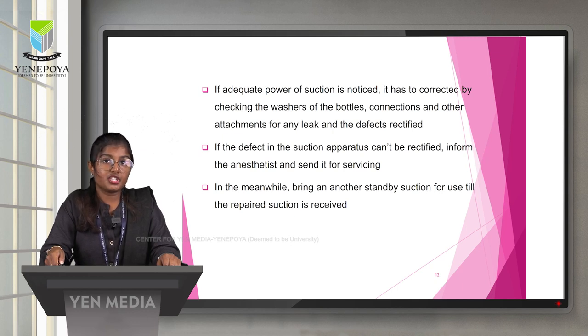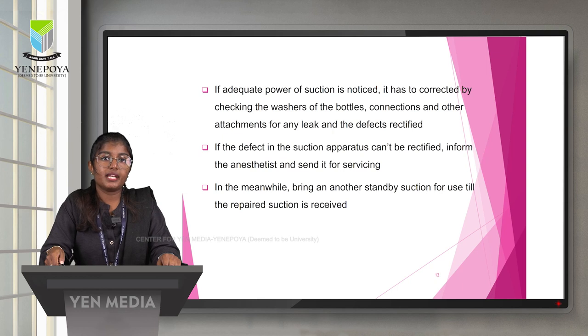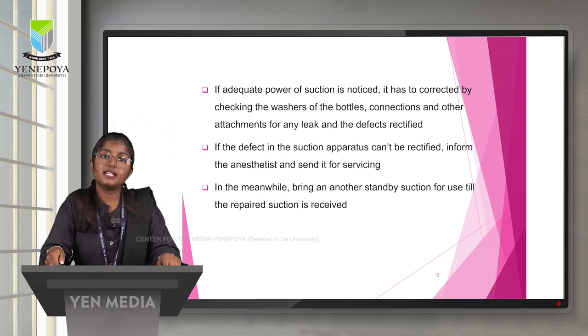If the defect in the suction apparatus cannot be rectified, inform the anesthetist and send it for servicing. In the meanwhile, bring another standby suction unit for use until the repaired suction is received.